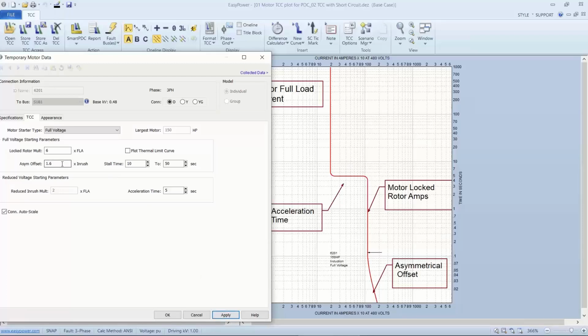Likewise, the asymmetric offset is a multiplier down here. Typical is in the 1 to 2 range. If we have a different understanding of the motor specifically, or if a different policy for a design, we would use a different factor for asymmetric offset. The stall times now. So this is, again, a normal starting curve. Any time current plot to the left of the curve would be considered a normal start. Any time current plot to the right side of the curve would be considered abnormal.